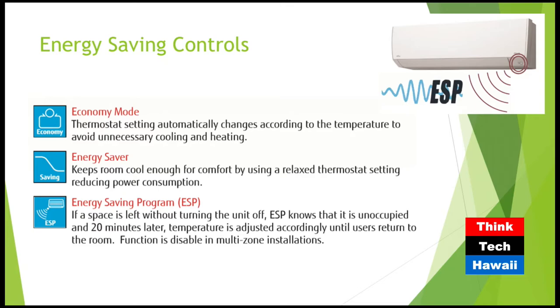The higher the set point, there's almost a logarithmic scale of energy savings according to the lower or higher set points. It's not like anybody walks into a hot, humid room, it just gets up a little bit, may feel slightly warm, but as soon as there's motion, the unit kicks on again and starts delivering cold air. That's what I mean about delivering cold air when you want it, as much as you want, just delivering the amount of energy you need for that cooling.